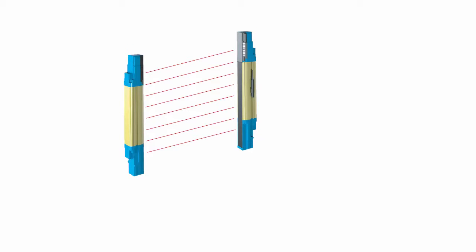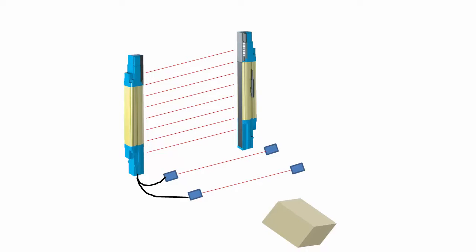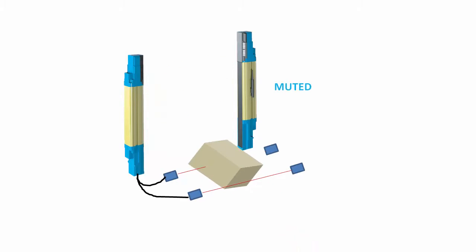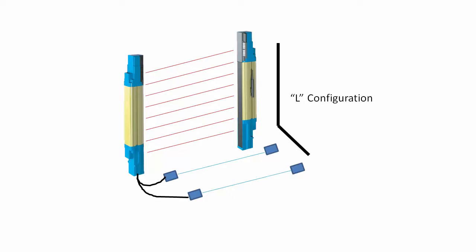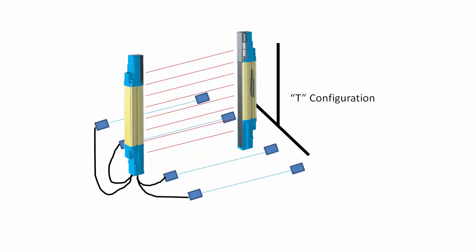The light curtain has some sensor inputs that it can monitor. You can then configure the light curtain to recognize if an object approaches at just the right rate from just the right direction, so it knows it's okay to let the object through without tripping the outputs. There is this L configuration which detects objects approaching from one direction and a T setup which can detect objects approaching from two directions.